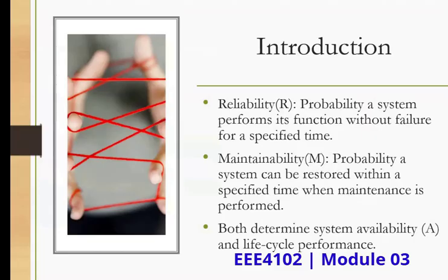If the unit is modular and is accessible, you can probably swap it out, let's say in 15 minutes. And if it is not a modular unit, whereby it is deeply embedded in complex racks and so forth, it may take you longer, like let's say 5 hours, to rectify the issue. Which means the second scenario demonstrates the lower maintainability, whereby it requires a lot of time for you to repair it.